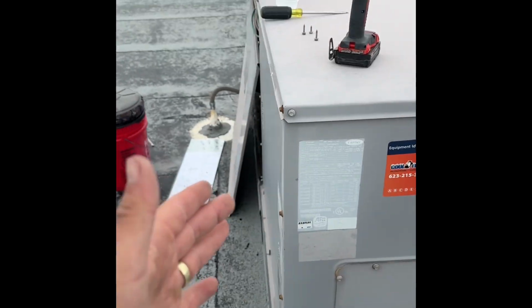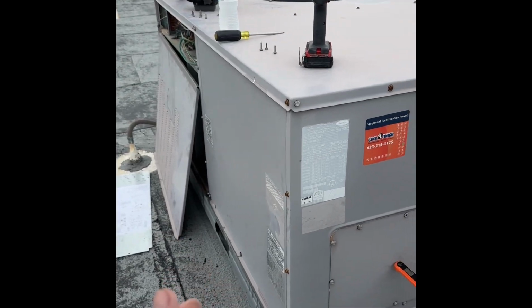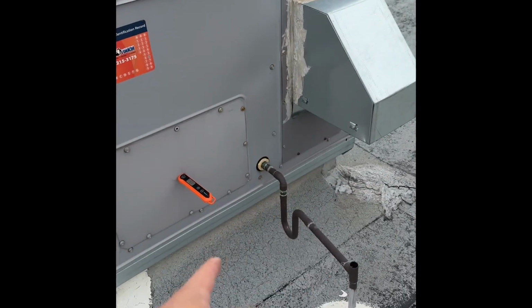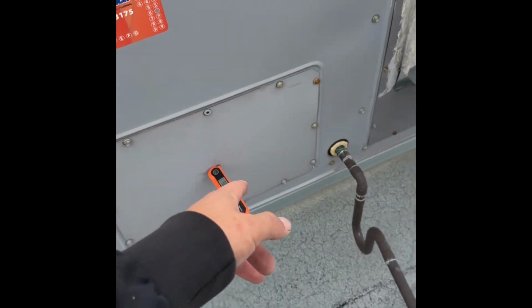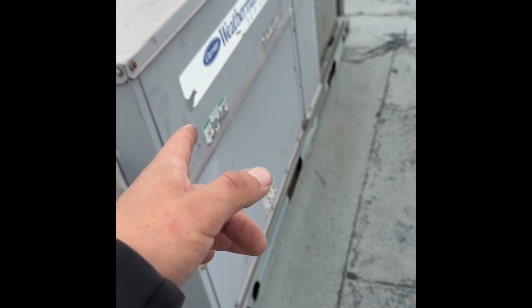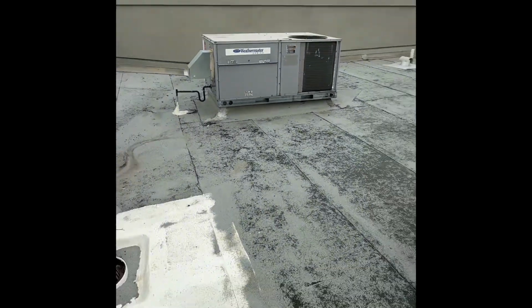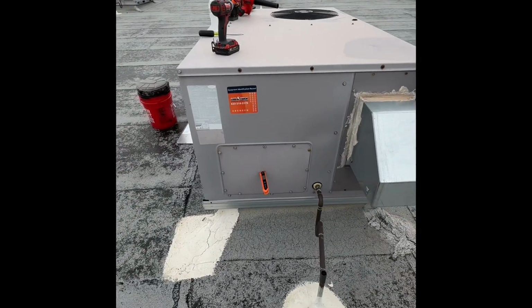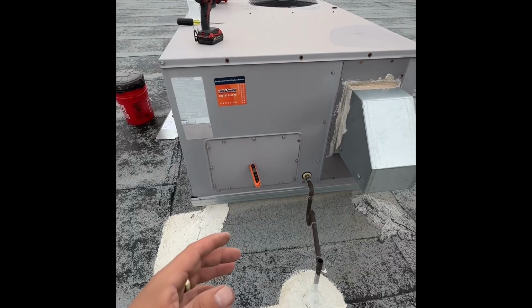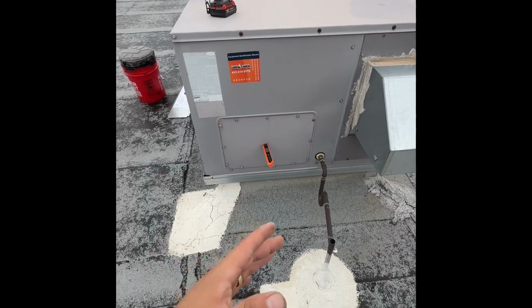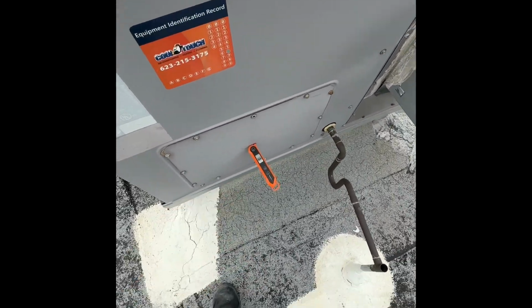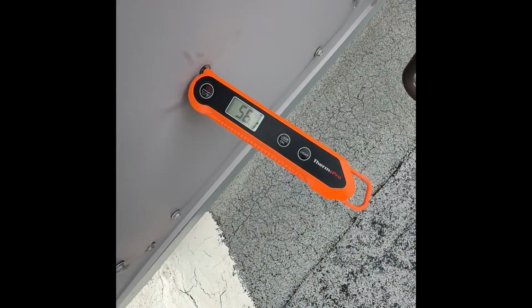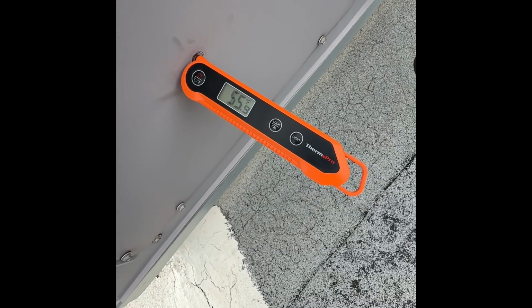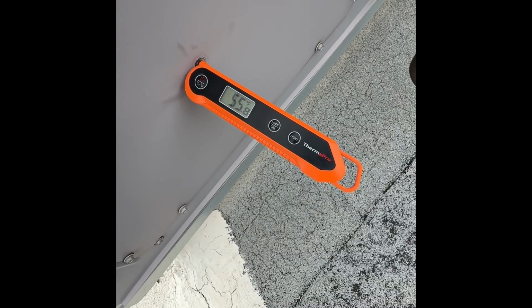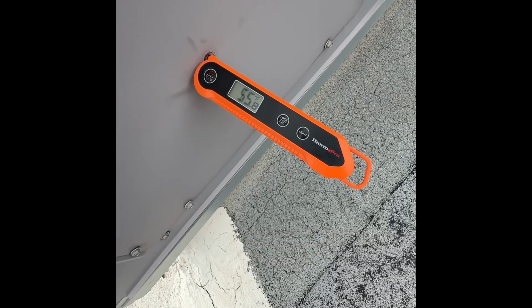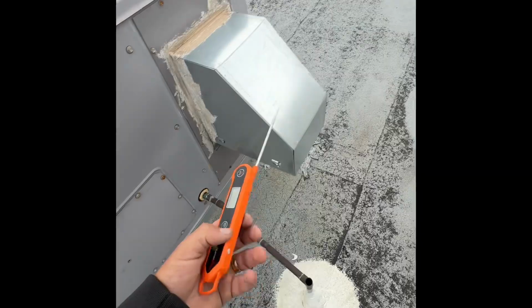So now we took care of amp draws, right? We got all that. Now we're gonna check our temperatures, our split, which is our supply air temperature compared to our return air temperature. Now, again, it is a little colder today than most days, so our return to supply split isn't gonna be the 15 to 17 degree ratio, which is the gap you want, but we'll try to get it close, guys. So right here we got 56, 55. Yeah, it's still dropping. Let's call it 54, 55, plus or minus 3 degrees, right?